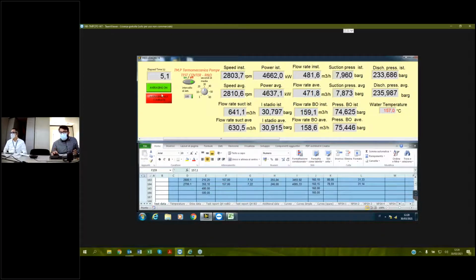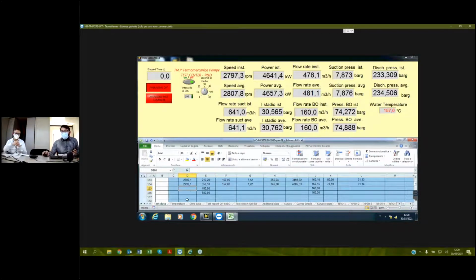After the first point of performance, we can check directly on the pump the vibration and the noise level. You can see that the software gives us on the second line different measurements, and the numbers are stable, so I can stop the average and I can write the data on the calculation sheet.